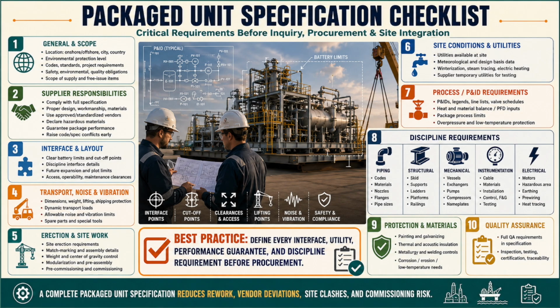Site utilities require the same discipline. Provide the supplier with available utility conditions: pressure, temperature, flow, voltage, frequency, quality, composition, and reliability. Include water analysis, meteorological data, and relevant design basis information. Do not tell the supplier that instrument air is available. State its minimum pressure, maximum temperature, dew point, quality, and design availability. Do not say cooling water available.